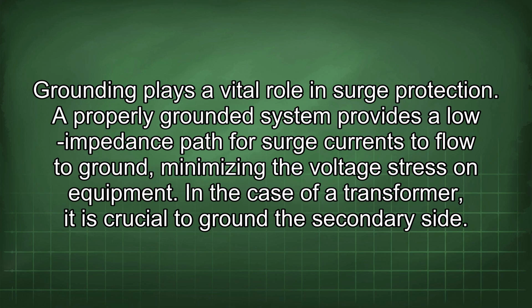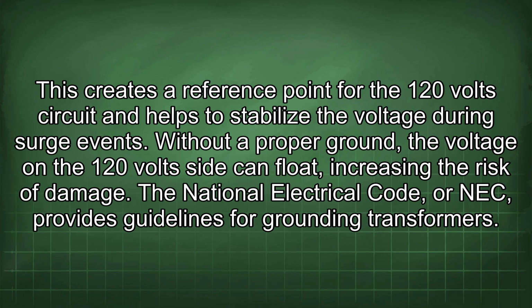A properly grounded system provides a low impedance path for surge currents to flow to ground, minimizing the voltage stress on equipment. In the case of a transformer, it is crucial to ground the secondary side. This creates a reference point for the 120 volt circuit and helps to stabilize the voltage during surge events. Without a proper ground, the voltage on the 120 volt side can float, increasing the risk of damage.